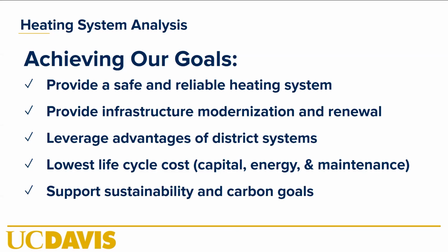So the path we're going is also 100% renewable, but a little more complex. But the challenge is that they both have a similar profile. If you look at what solar thermal does, you get all your heat out of the solar thermal in the summer, and you get a lot less in the winter. Same with heat recovery, right? You get all your heat recovery in the summer when you're doing all your cooling, and you can recover that heat. In the winter, you don't have enough.